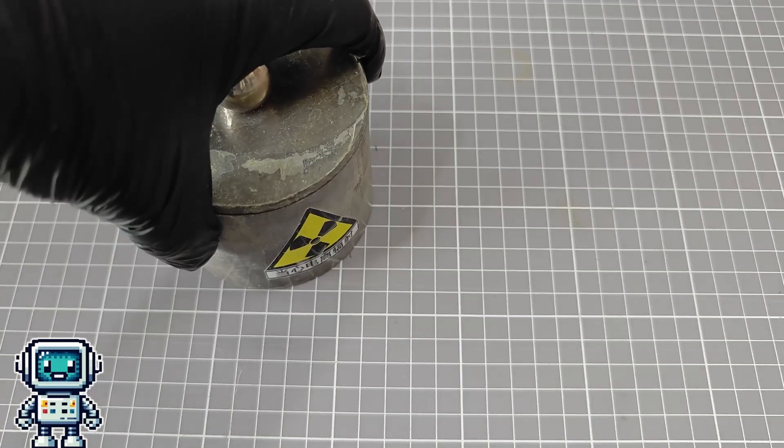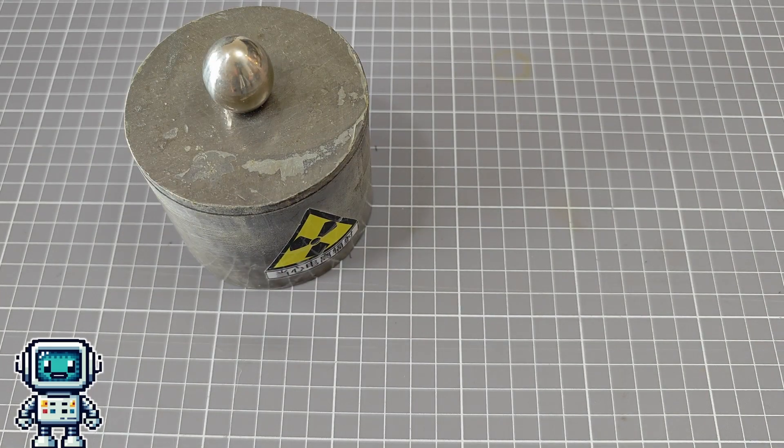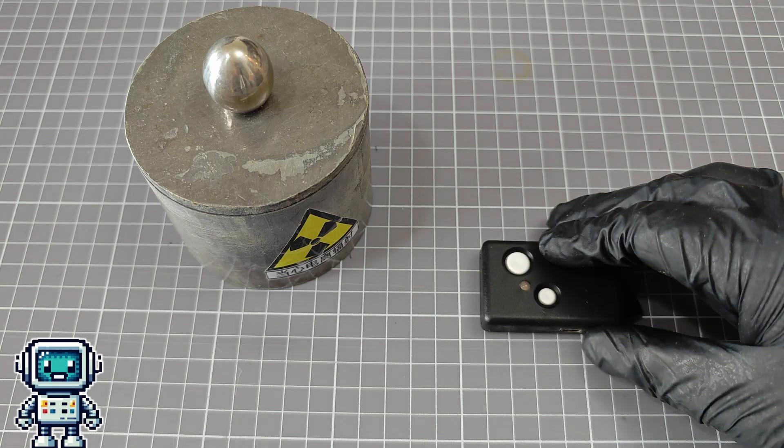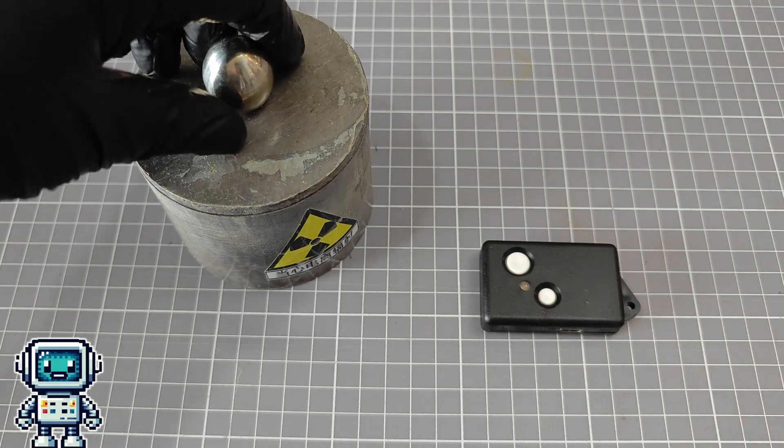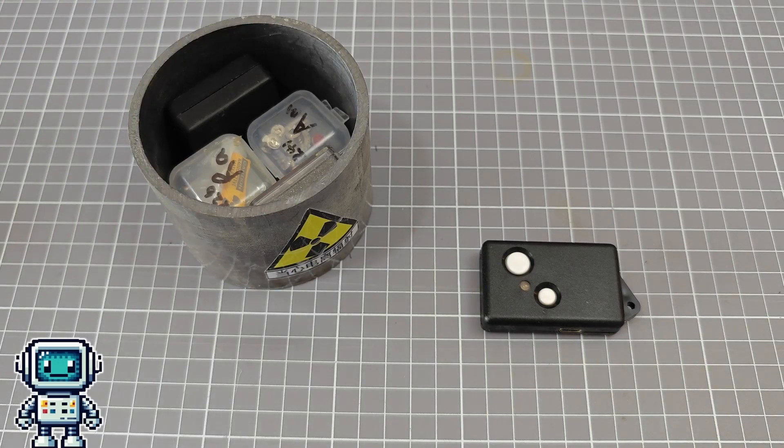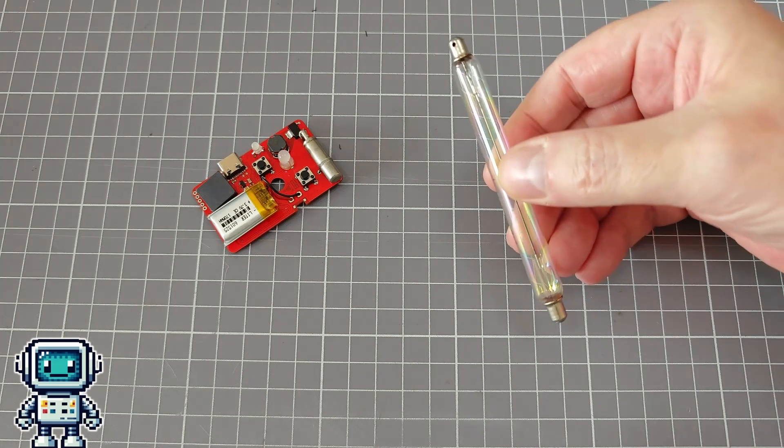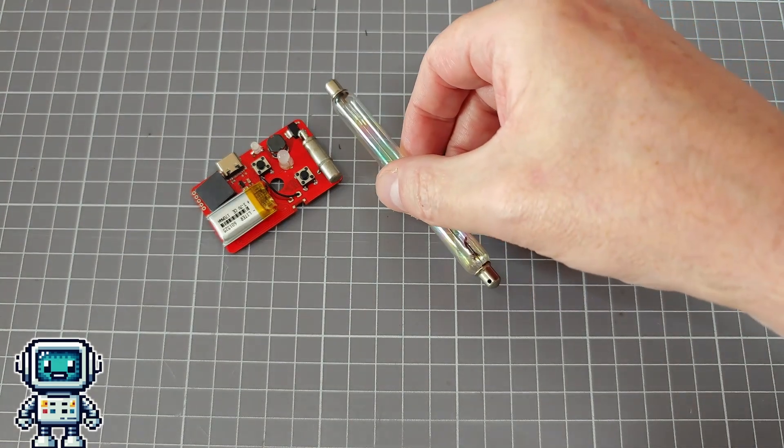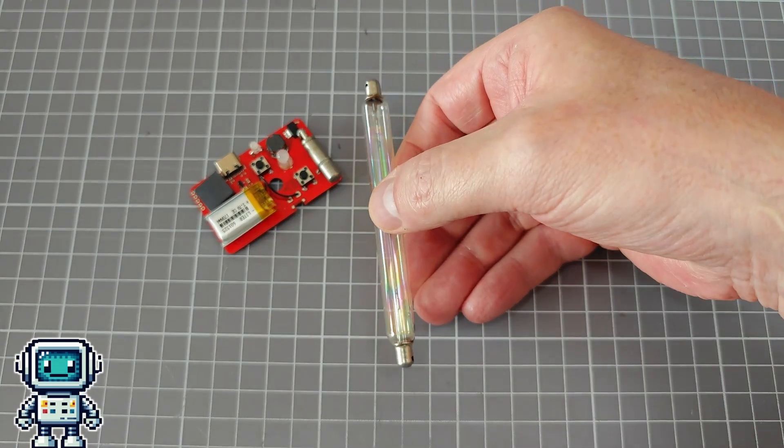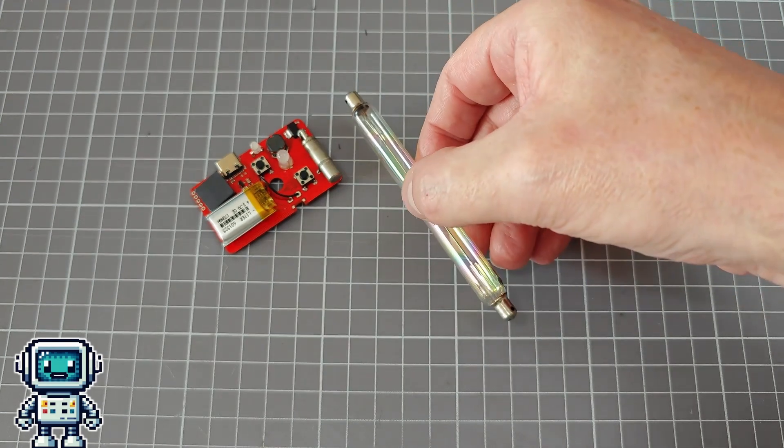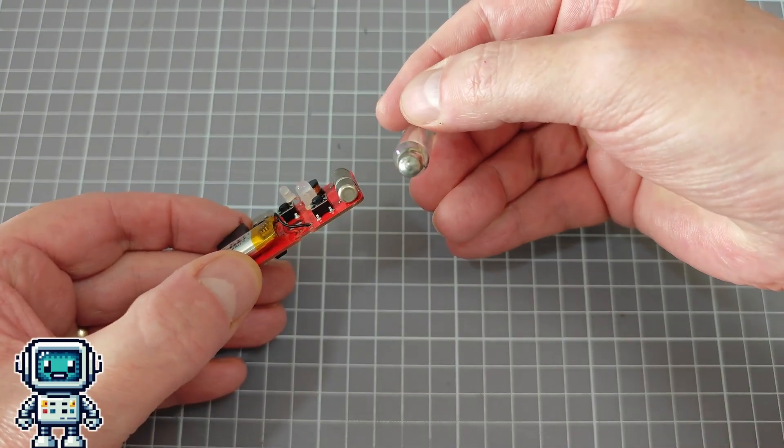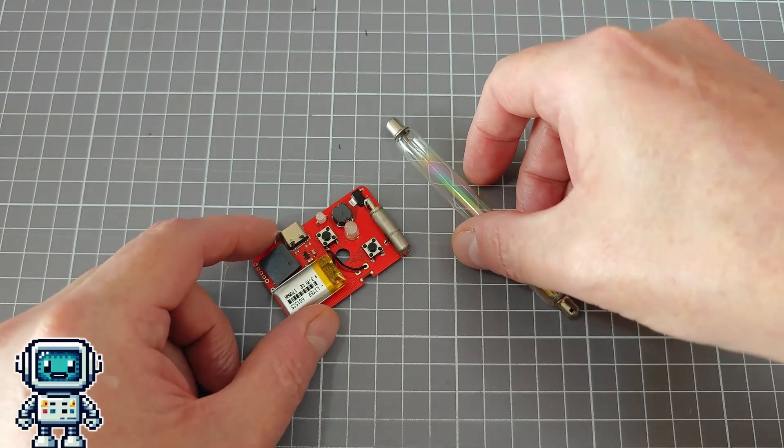Well, it's time to break out the radioactive test sources and give this thing a real shakedown test. From the teardown of this device, we know a couple of important things about this product. Firstly, that it is only sensitive to gamma rays and to hard beta particles. We also know that the sensitivity cannot be expected to be very high. The Geiger muller tube inside this device is absolutely tiny, so we should expect the response to be lower by the same proportion.